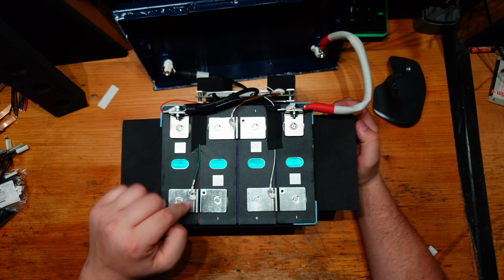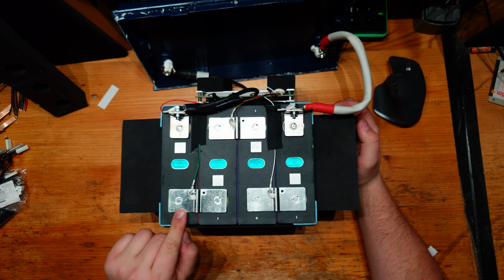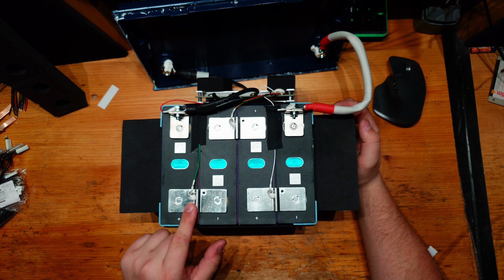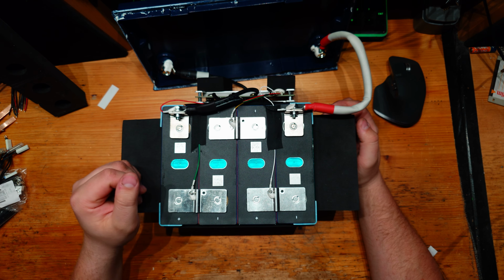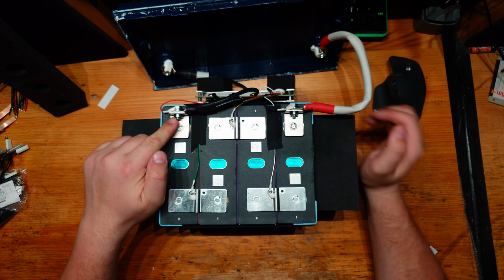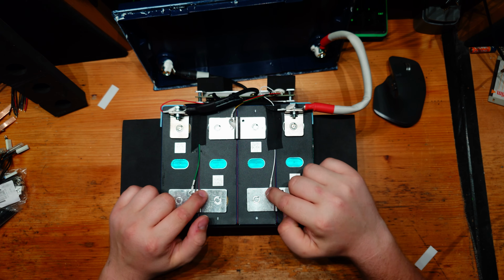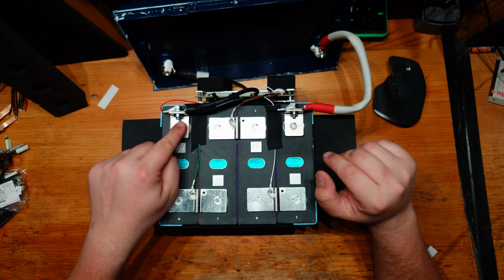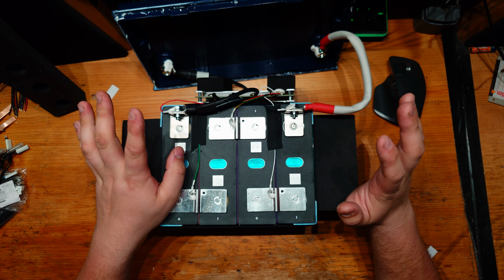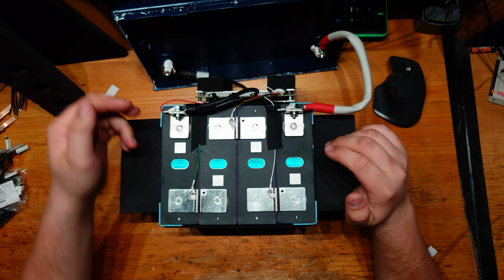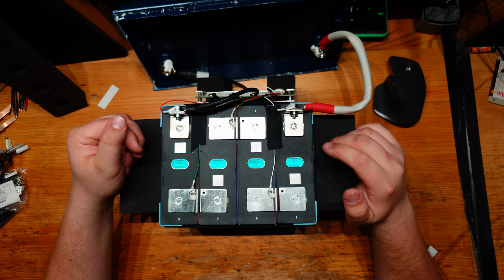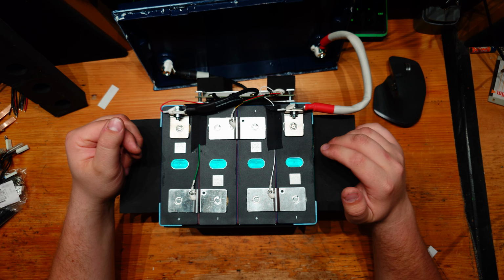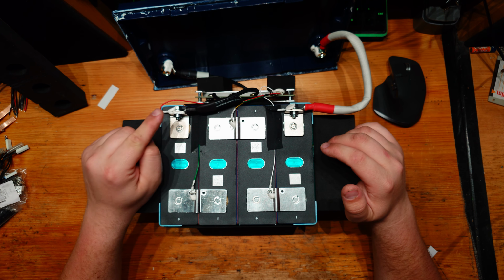The cell interconnections are welded on aluminum sheets with dilatation stress relief in the middle. All the threaded holes for bolts, which means the main power connections as well as the balance connections, have push-in steel nuts, which is great. I mean, if they would just tap a thread in the aluminum piece, the thread would be too soft, so steel nut inserts are very fine, and I like to see that.